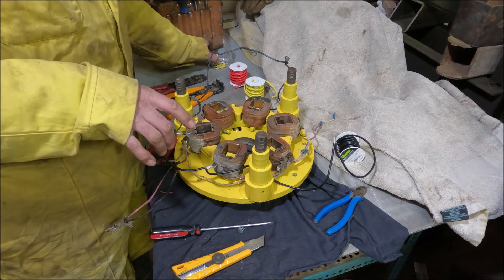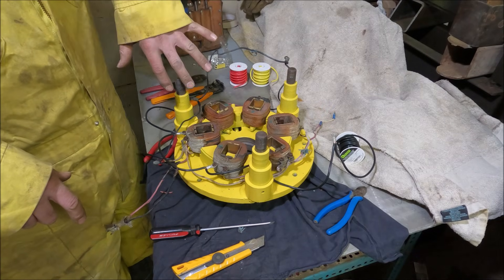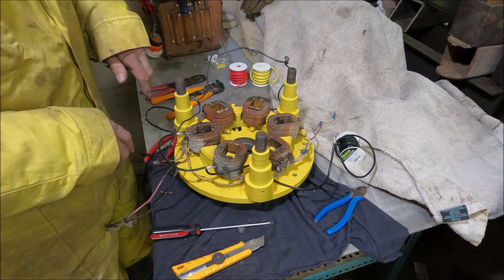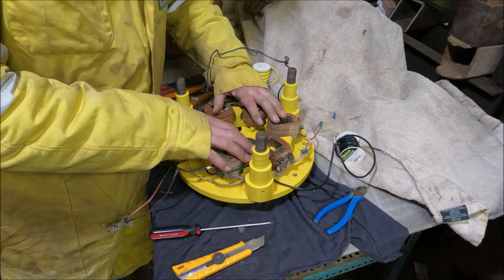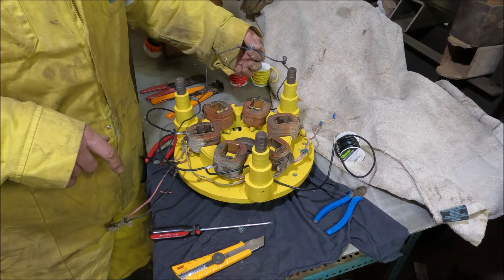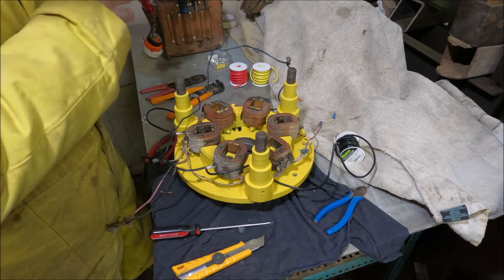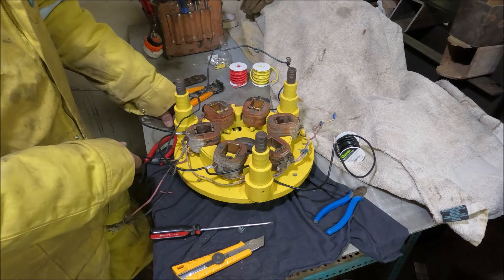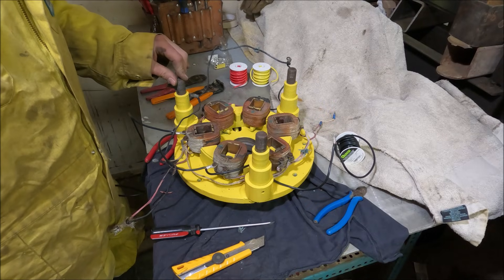I have a wiring diagram of this. It looks like four are connected, then another four are connected, and then two more from a third wire. I believe this is all three-phase, or single-phase branched off one of the three phases. I'm just following what was here, and what was here matches what's on the drawings - that gives me confidence that I can refurbish this wiring to what was here. Hopefully there's no funny business, but it's coming along.